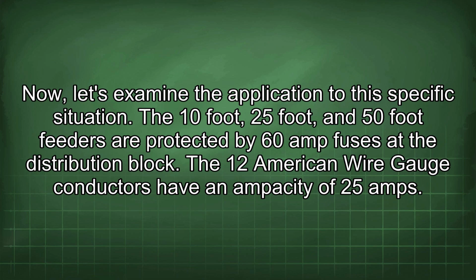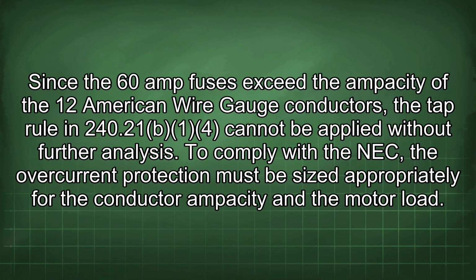The 12 American wire gauge conductors have an ampacity of 25 amps. Since the 60-amp fuses exceed the ampacity of the 12 American wire gauge conductors, the tap rule in 240.21 cannot be applied without further analysis. To comply with the NEC, the overcurrent protection must be sized appropriately for the conductor ampacity and the motor load.